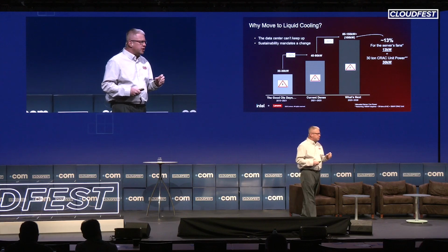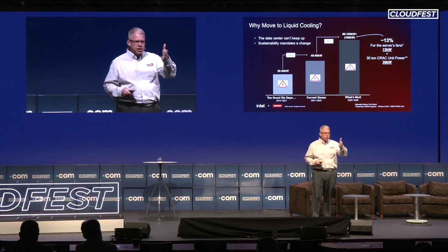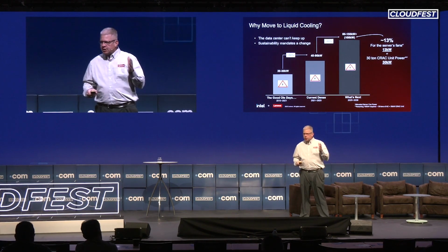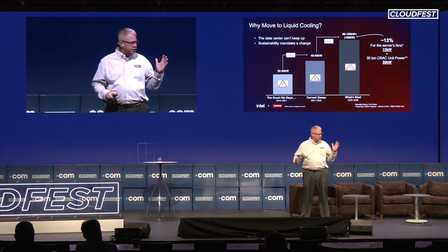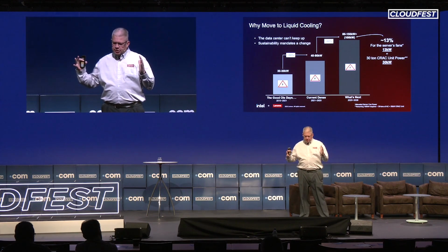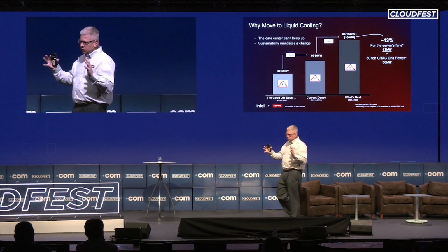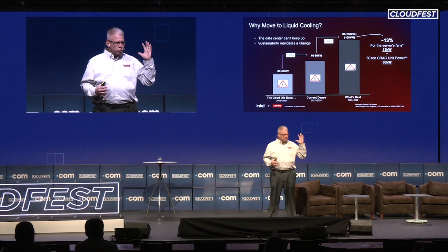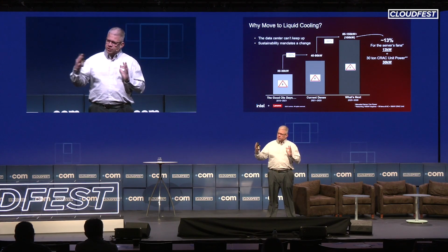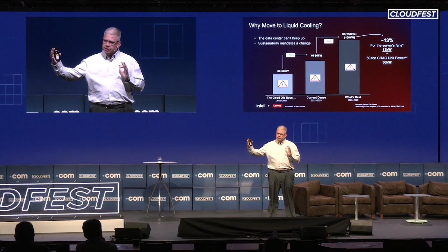So if you take those numbers and say, on a 100 kilowatt rack, what do you need to do to actually cool that? About 13% of the power you're going to put into that 100 kilowatt rack is simply to move air from the front to the back of that rack. That's 13 kilowatts worth of power just to move cool air from the front, remove heat from the server, and bring it to the back.